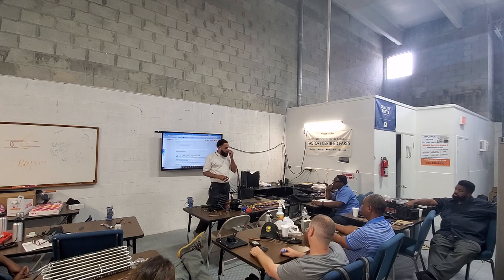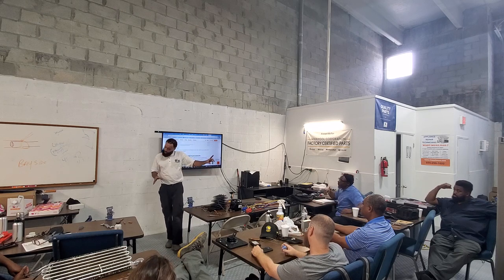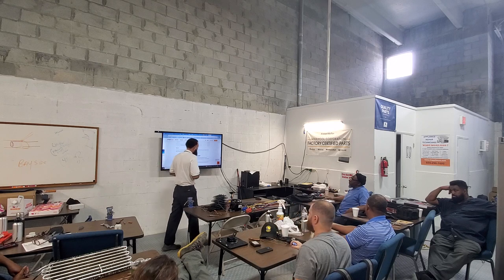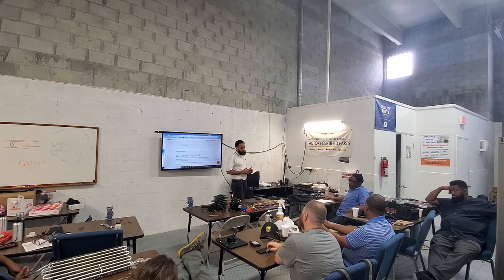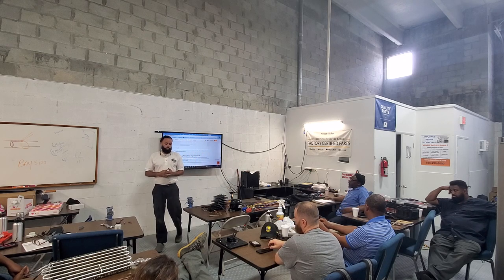How deep into the vacuum do we bring it? And then once we're there, for how long do we stay? As you said, you bring it in first, you go at a 10, and then see if it goes back up. And the next one will be a 30.